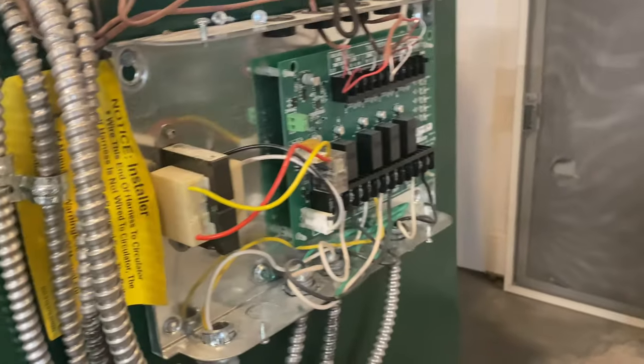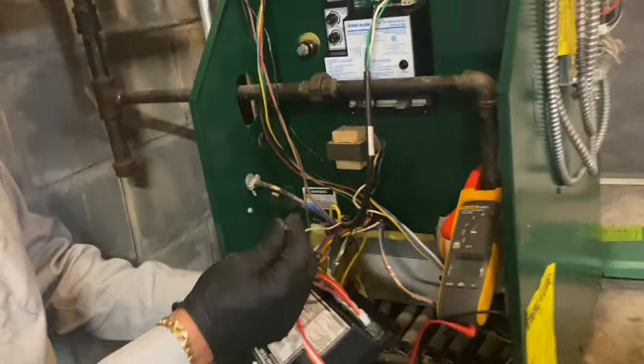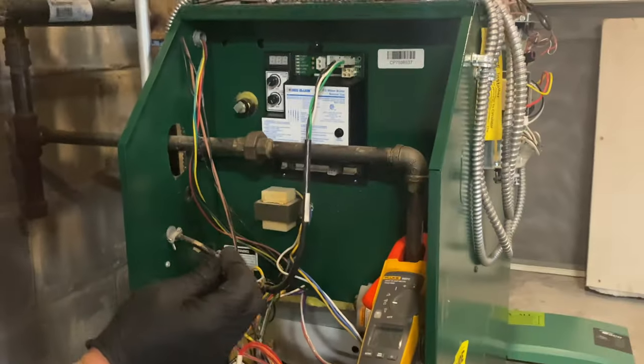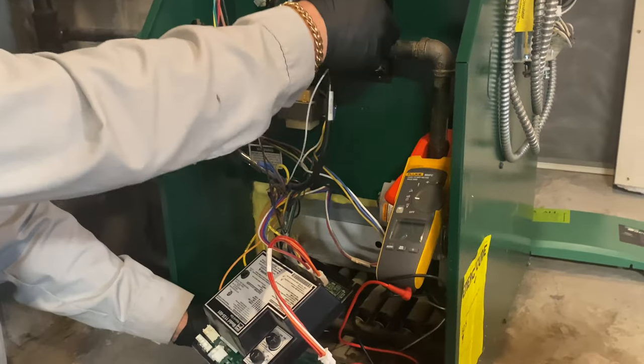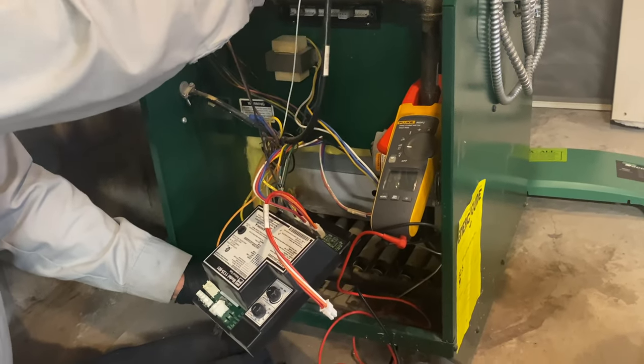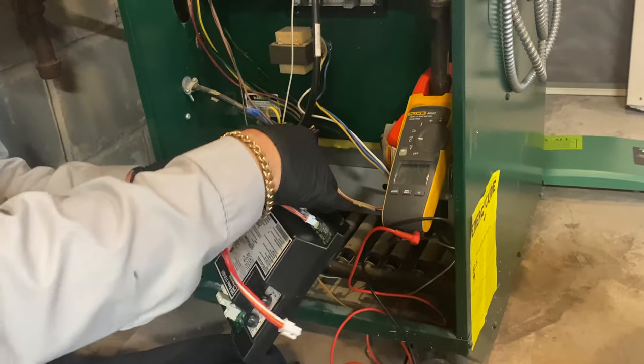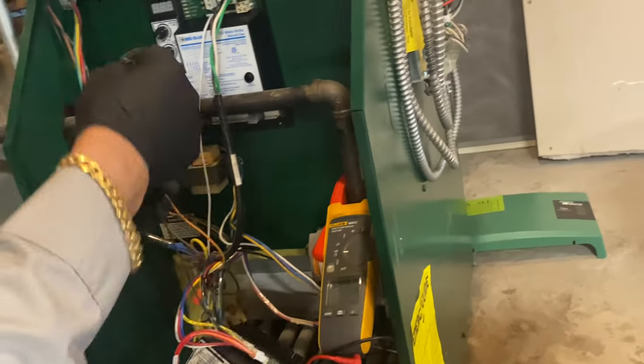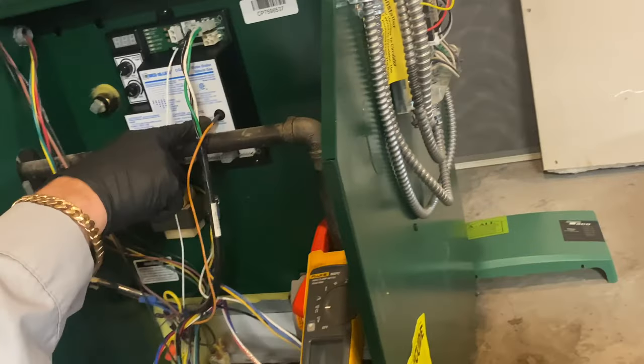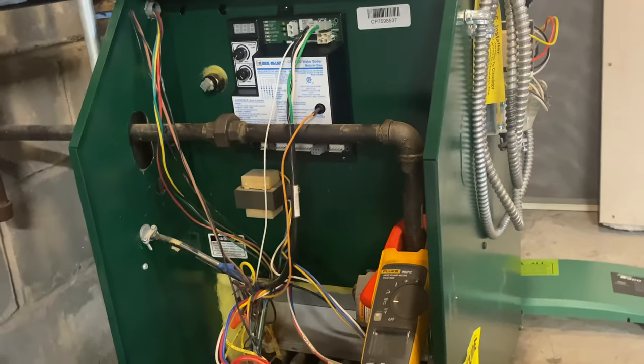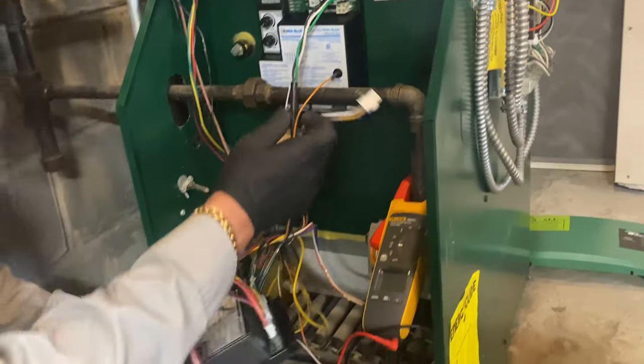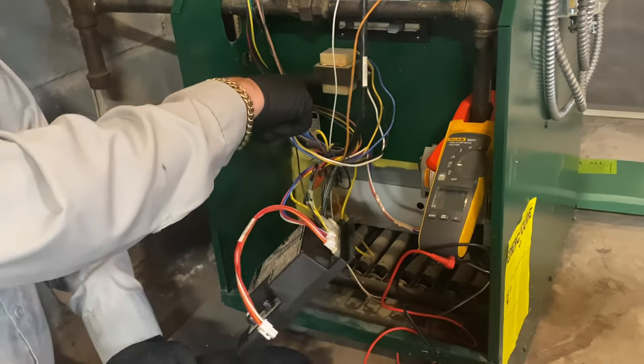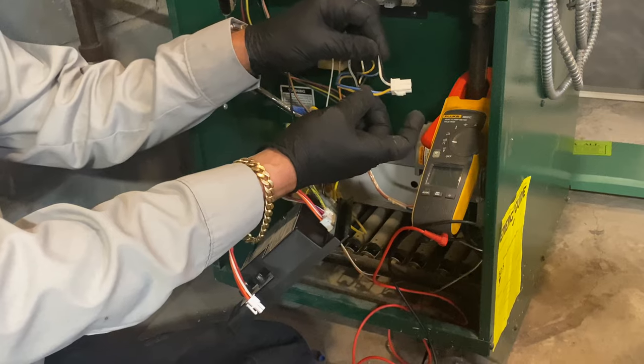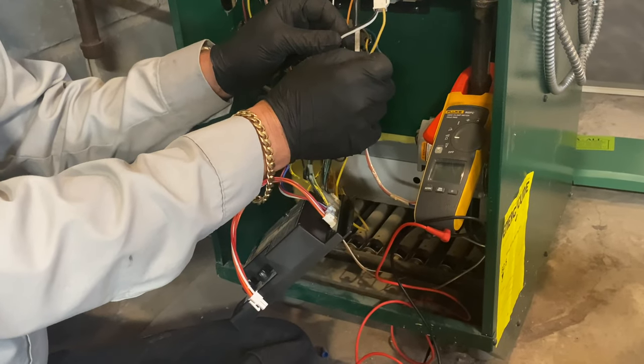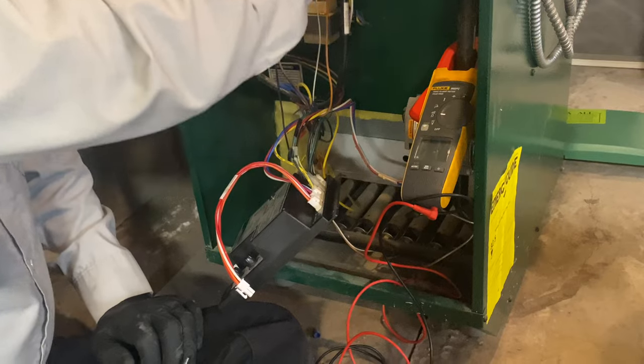Okay, so we won't be dumb as we put things back in. Now, this white wire is our sensor. The orange is our spark, goes there, high voltage, pilot sense, pilot flame, okay? And we have this, which is our transformer. The black and white is line voltage, the yellow and blue is low voltage. So that goes in right there.